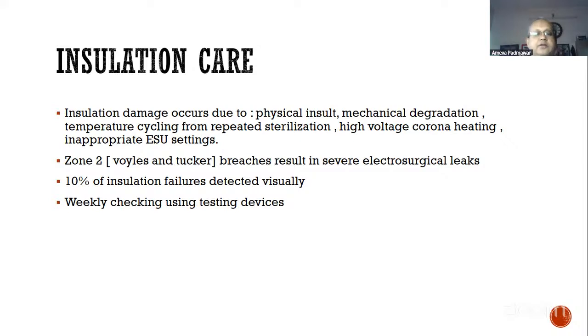So especially, there are different zones of the instruments which have been described from where these electrosurgical leaks can occur, especially the one from beyond the jaw to the handle of the instrument, which is actually not seen while doing the surgery. And any breach in this insulation is going to cause leakage of current and damage. But physical inspection will detect only a few breaches, especially when the rent in the insulation is large. Otherwise, it is very likely to get missed out. So your CSSD department or the biomedical technical team should inspect the instruments once in every week or once in a fortnight, depending on the number of surgeries which are going on in your institution or hospital.